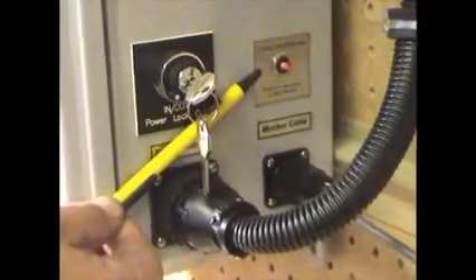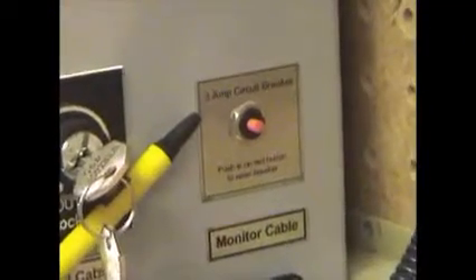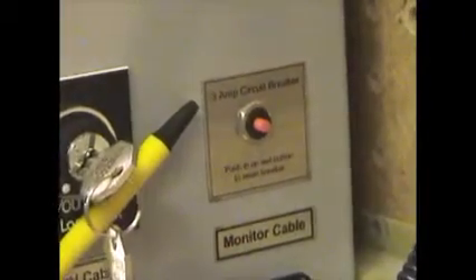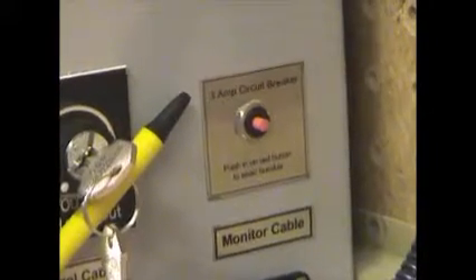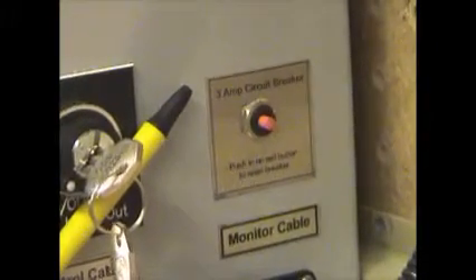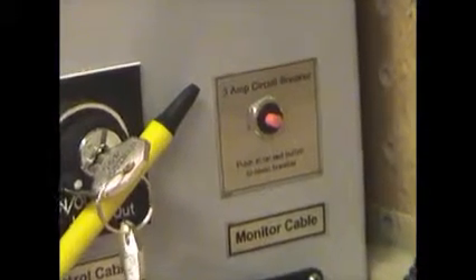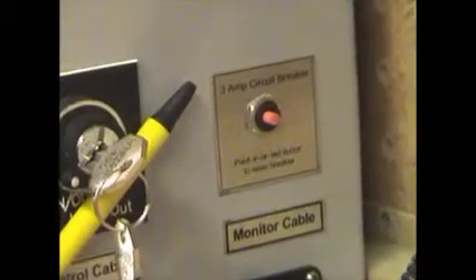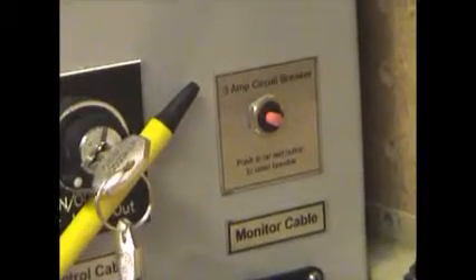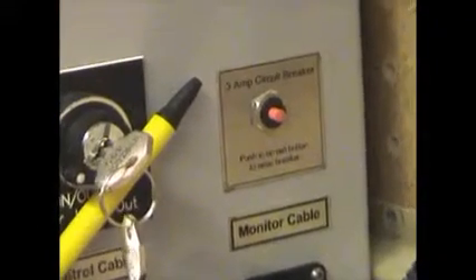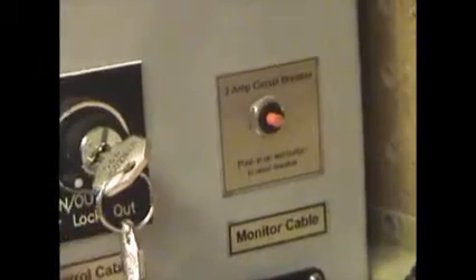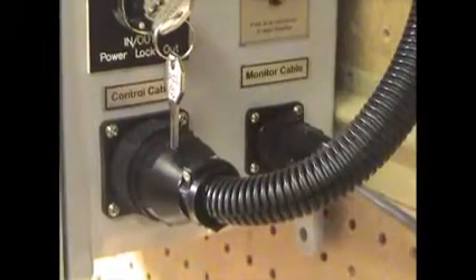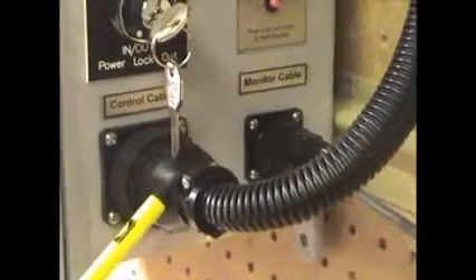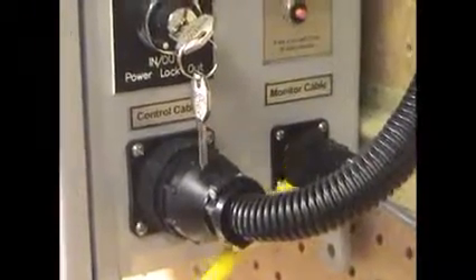Next to the lockout switch is a 3-amp circuit breaker. In the event an electrical short should occur, the circuit breaker will trip, preventing current to be supplied to any of the Dredgemaster electric components. Once the shorted component or wire is repaired, it will be necessary to push in on the button of the circuit breaker to reset it. This will allow electric current to flow to the Dredgemaster electrical system. On the bottom is the main electrical harness connector and the monitor harness connector.